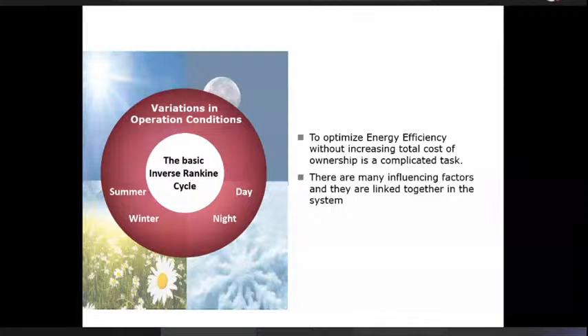This is called the condition of shifting loads. Now shifting loads, let's for a moment assume that the evaporator side is constant. So we are happy with 25 degrees and we want to maintain it at 25 degrees centigrade all the time. Now if the compressor has a constant capacity, it will not be in a position to follow the basic inverse Rankine cycle.